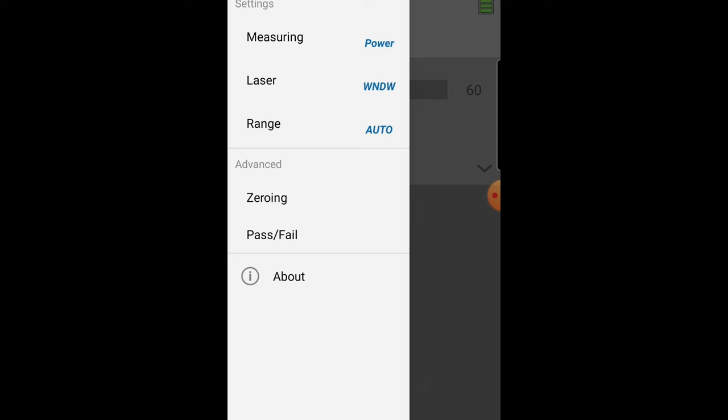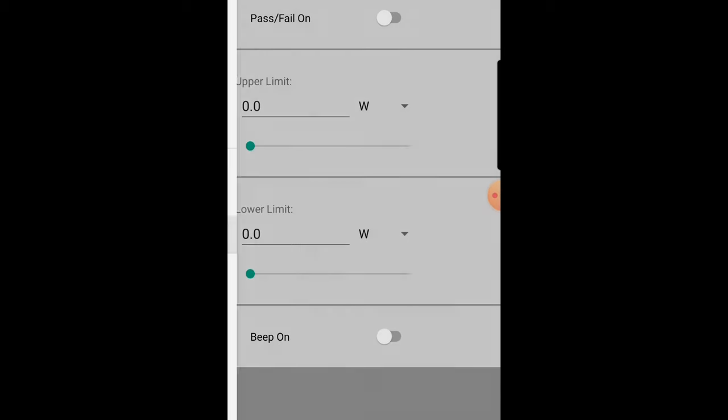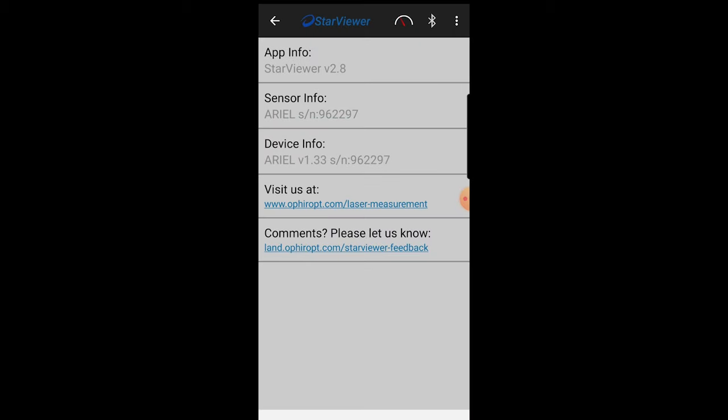Pass-fail lets you set upper and lower limits and get a warning if the power goes above or below those limits. Info displays basic information about the app and about the ARIEL unit.